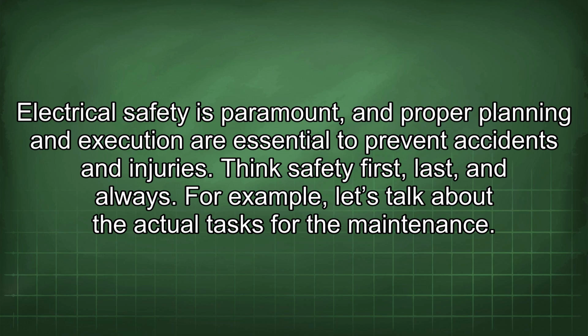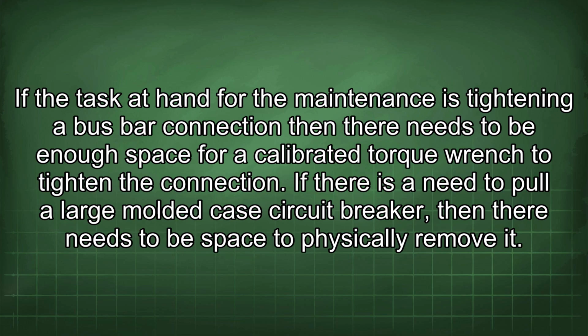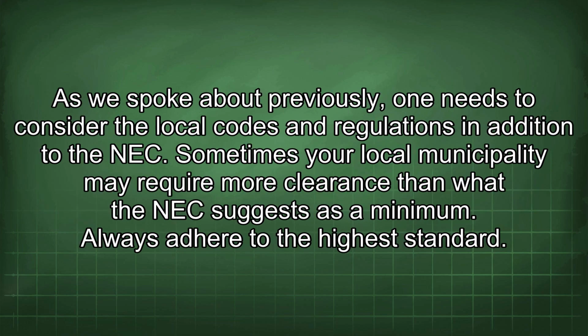For example, let's talk about the actual tasks for the maintenance. If the task at hand for the maintenance is tightening a bus bar connection, then there needs to be enough space for a calibrated torque wrench to tighten the connection. If there is a need to pull a large molded case circuit breaker, then there needs to be space to physically remove it. As we spoke about previously, one needs to consider the local codes and regulations in addition to the NEC. Sometimes your local municipality may require more clearance than what the NEC suggests as a minimum. Always adhere to the highest standard.